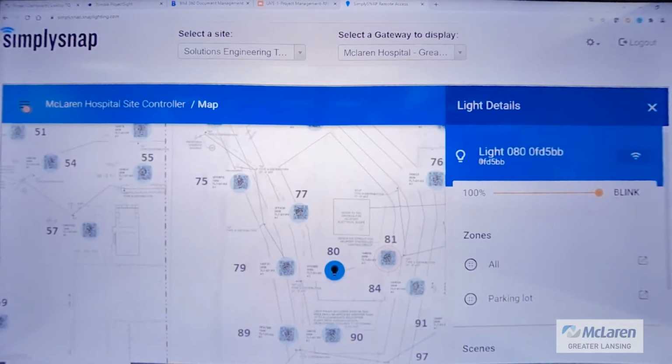From the top of the poles, the controllers themselves that are communicating have an address. That's actually where we got the information here, but they have a little sticker on them that has this address. So you'd have to have a lift to get out there. But if you got on the lift and got to the top, you could figure out which address matches up to that pole and figure it out that way. You could also just log in the system and turn off lights. That's how I did it yesterday, trying to figure out where I was in the lot.